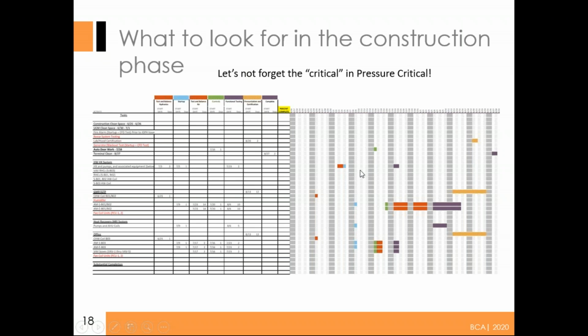So one thing that we do in our critical projects is, if you've heard of pull planning, where you do a schedule with all the subcontractors but you start at the end of the project and work forward. Even when they do that, they typically still don't give very detailed end of project schedules, basically where you start having equipment startup, test and balance, controls. So as part of our commissioning effort, we'll do a pull plan with just the contractors, and we pull from turnover back to where equipment startup is. This was going to be an FDA certified clean room lab, so we did a day-to-day schedule for the last two months.